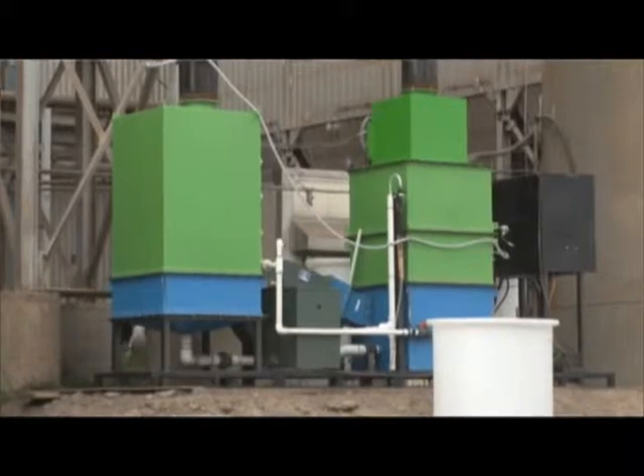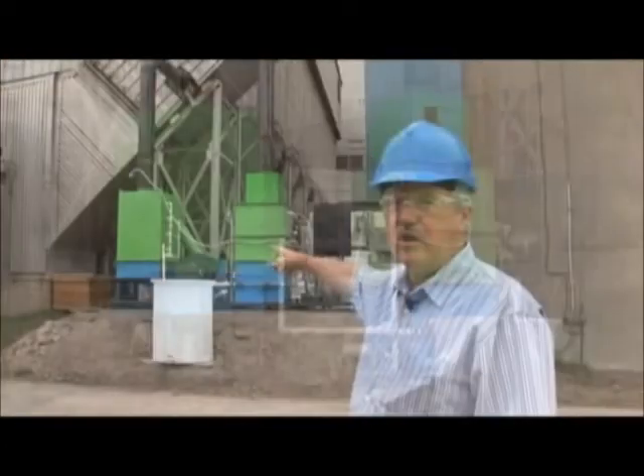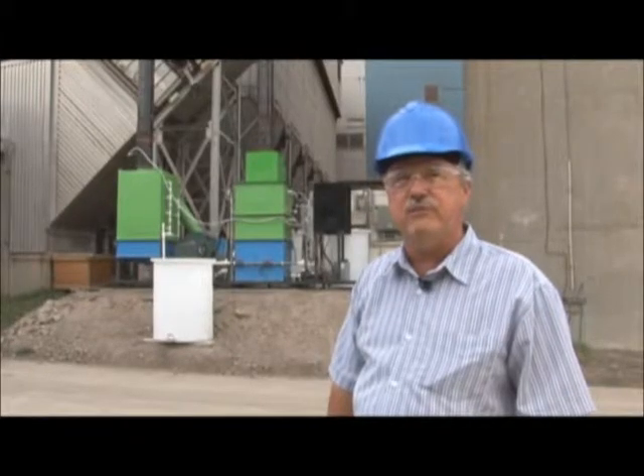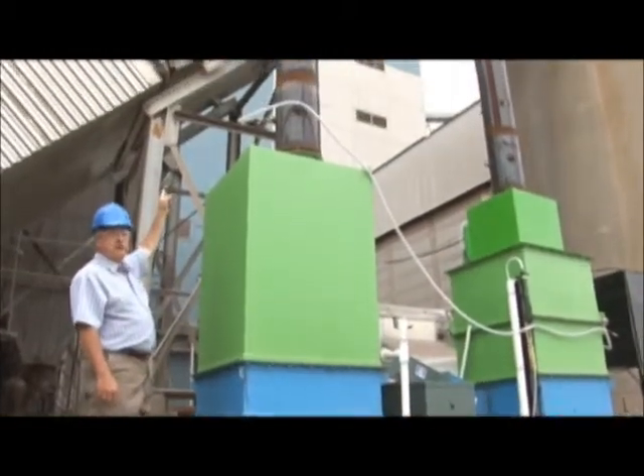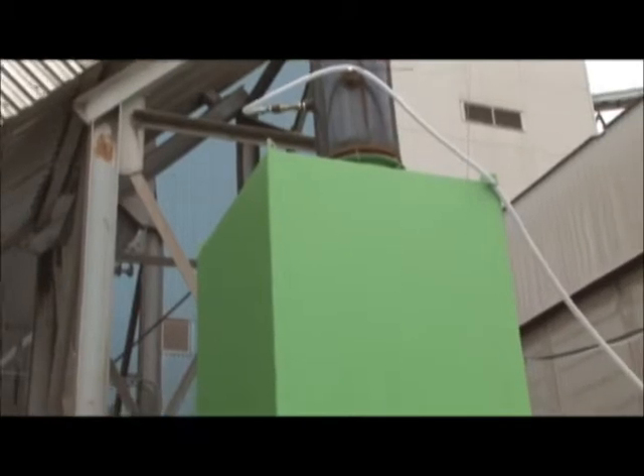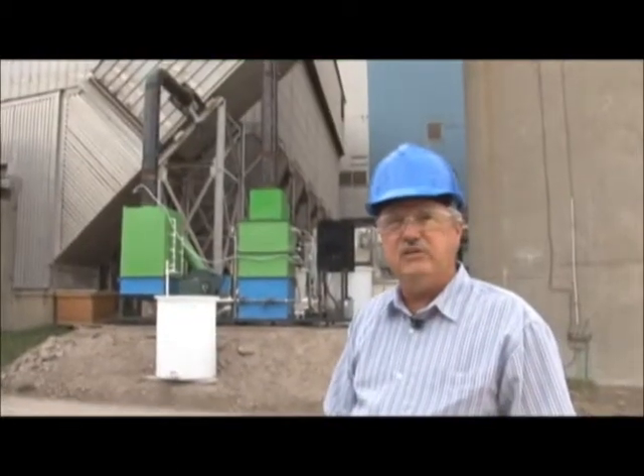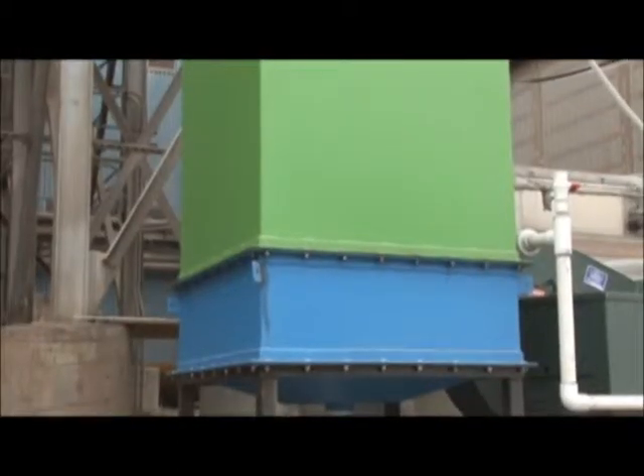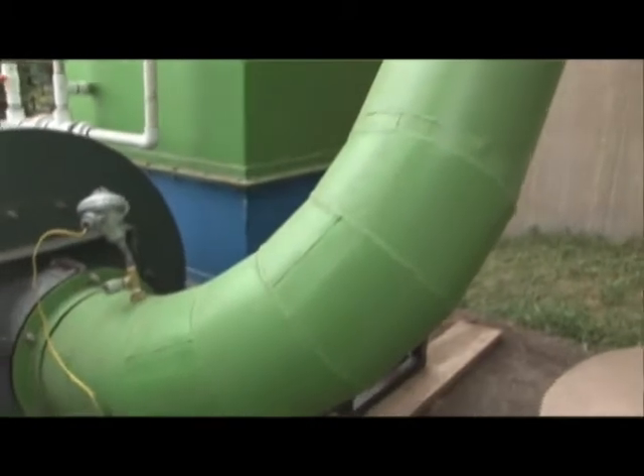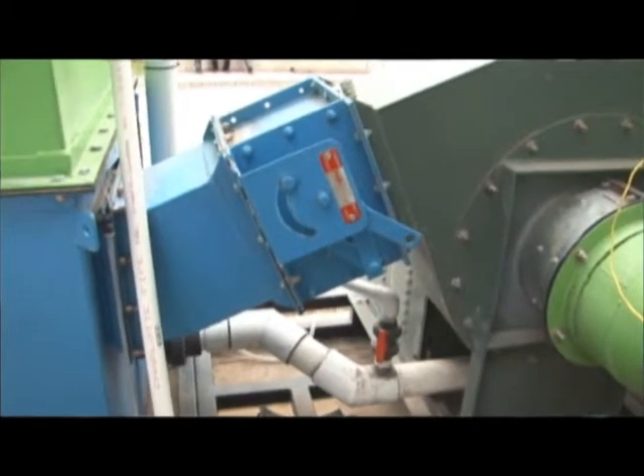We're pulling it into the left side process column where the gas conditioning chamber is cooling the gas. We then push it through a blower and into the actual scrubbing heads to remove the sulfur dioxide from the flue gas. The gas is drawn from the breaching after the ID fan. We draw a slipstream down into this gas conditioning chamber here — a chamber divided into two compartments where spray is added, cooling the gas to about 60 degrees Celsius, and performing some neutralization of the sulfur dioxide. The gas is then directed through a blower and into the scrubbers. There are two scrubbing heads on the scrubber.